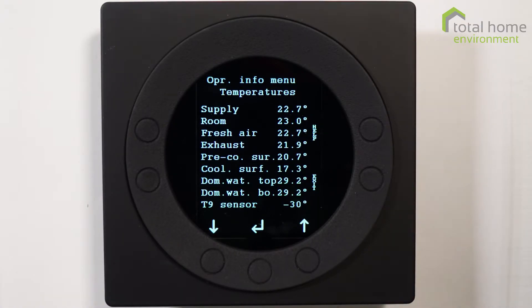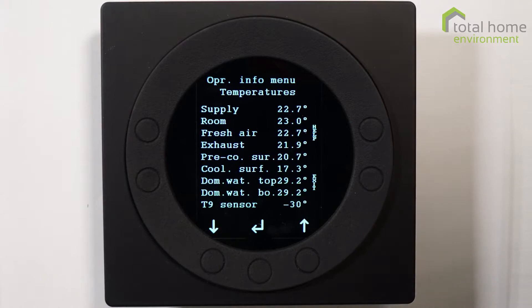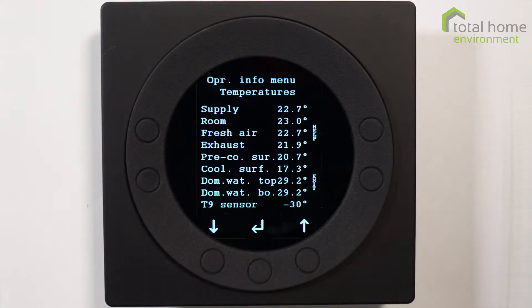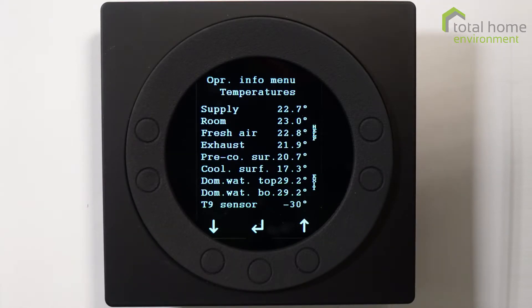Room temperature is actually where this controller is, and there's a sensor just in the bottom which gives us a temperature. Fresh air is fairly obvious - that's the temperature of the air coming in from outside. Exhaust is the temperature of the air going out. Pre-cooling surface is the temperature between your passive heat exchanger and your evaporator coil. For most of us that's not really important, but for guys wanting to service it or to identify a fault, it's a really useful parameter.